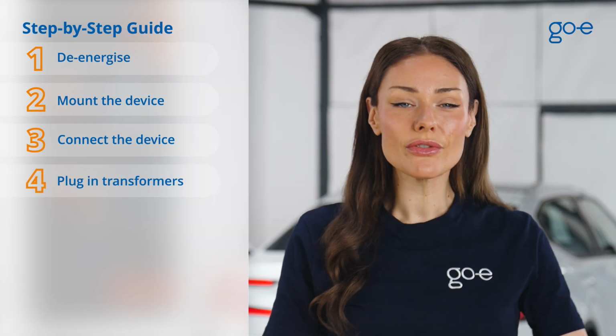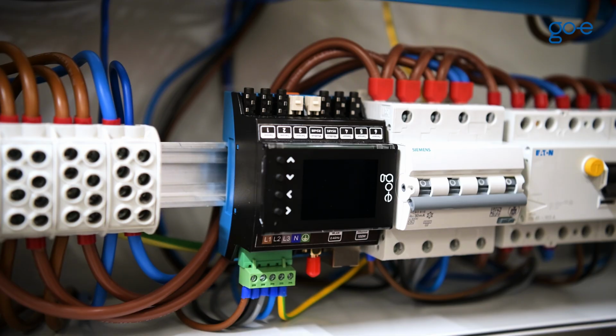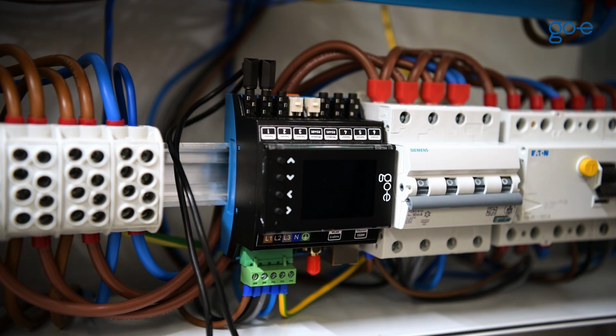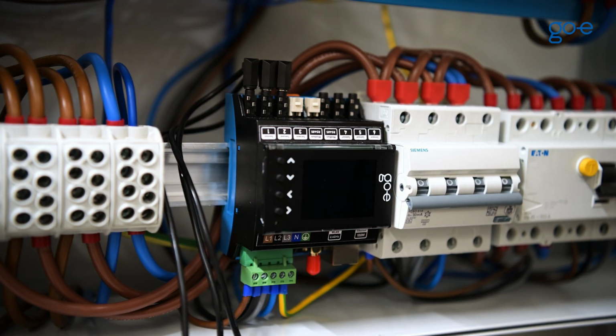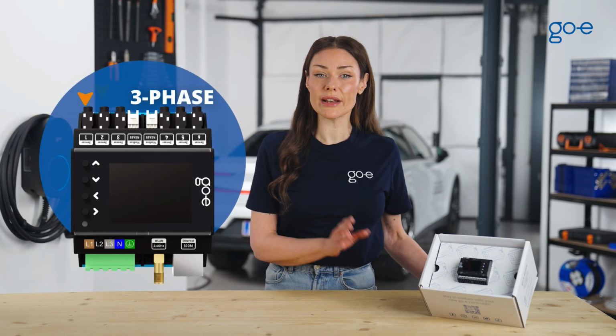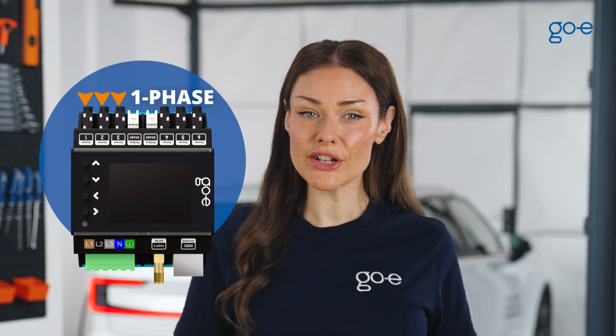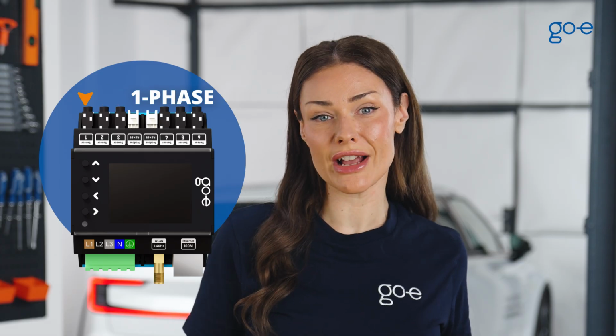Step 4. For a 3-phase connection, plug the jack plugs from the 3 current transformers into the corresponding inputs for current measurement. For example, into sensors 1 to 3. For a single-phase connection, you'll only need 1 current transformer.